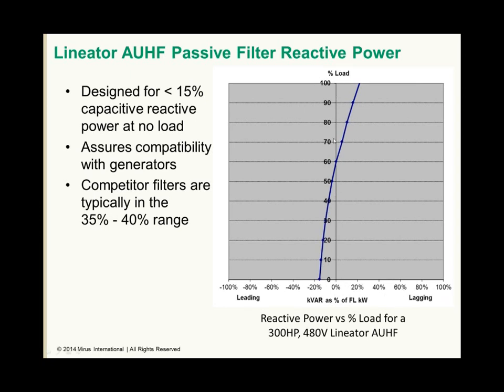The y-axis is our loading. And at no load, we're at 15% or less. As we start to load up the filter, the capacitive reactance drops. Well, at 60%, we introduce no capacitive reactance, and then we become inductive as we continue to load up the filter. So we will guarantee less than 15%. Competitive filters are typically in the 35 to 40% range.